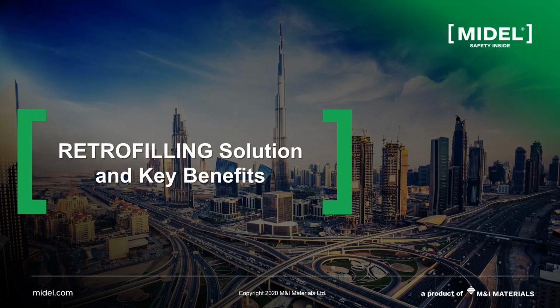Now, so far, if I just summarize what I've been talking about, I introduced esters, the key benefits of fire safety and biodegradability, and how they compare in that table with mineral oil. And then we reviewed the basics of the transformer design aspects, electrical design aspects and thermal design aspects. I mentioned that for the electrical design aspect, the most important parameter to consider is the permittivity, which will alter how the stress is distributed within your insulation system if you are using an ester instead of mineral oil. And the last one is the thermal design aspect.